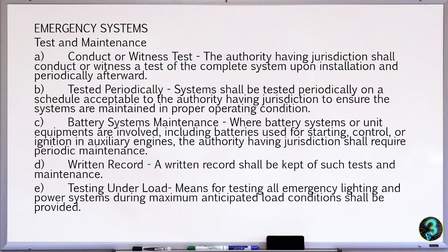So if you have a battery system maintenance, where battery system or unit equipment are involved, including batteries used for starting, control, or ignition in engines, the authority having jurisdiction shall require periodic maintenance. Then also a written record of the test shall be kept, no? Then testing under load: means for testing all emergency lighting and power systems during maximum anticipated load condition shall also be provided to the emergency system.